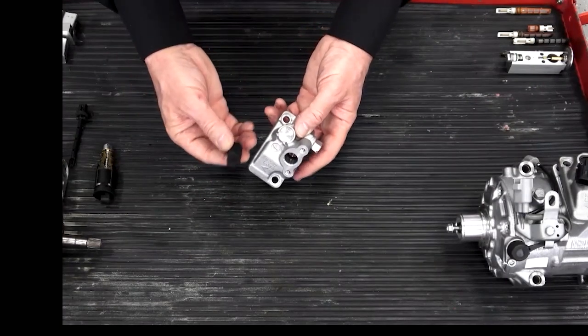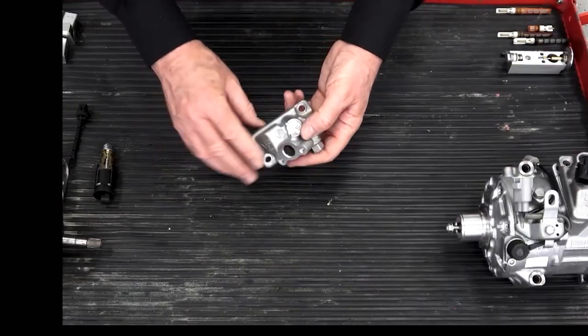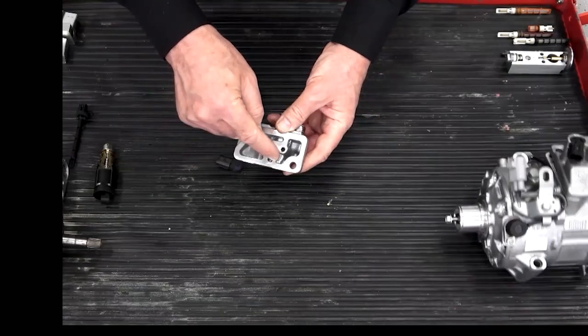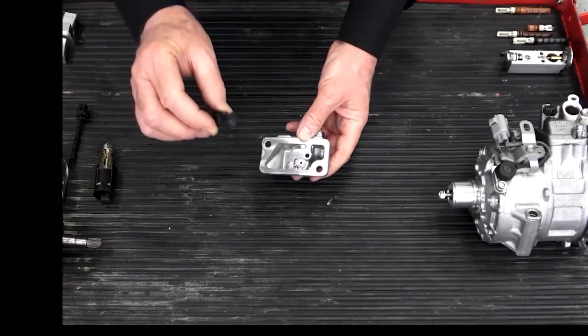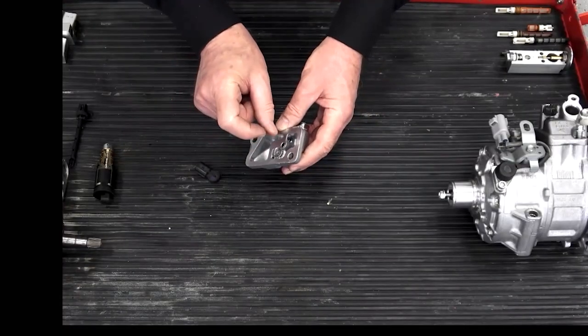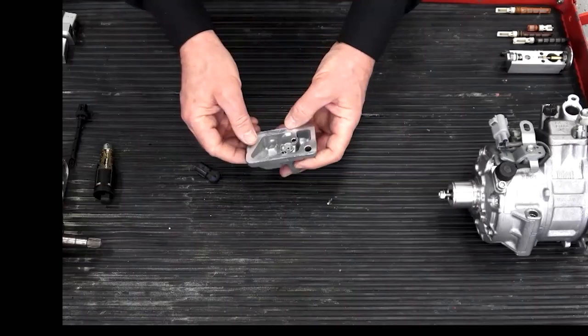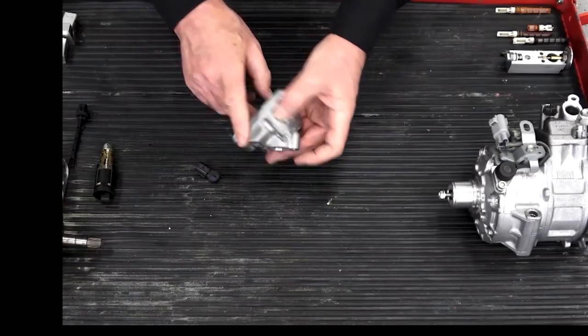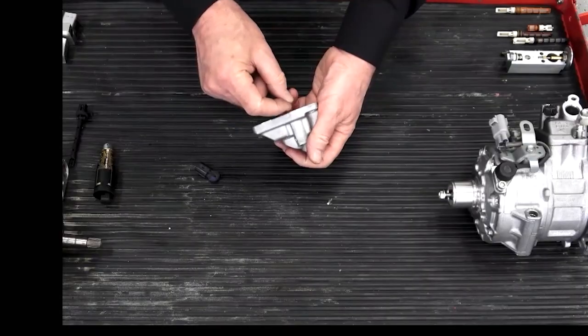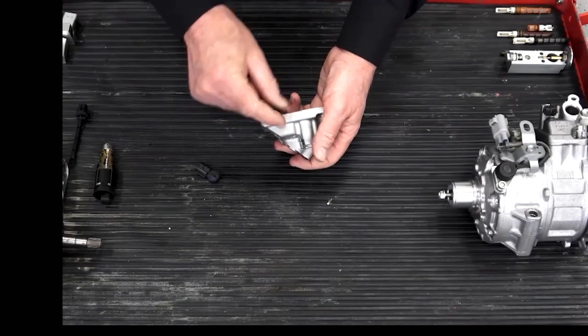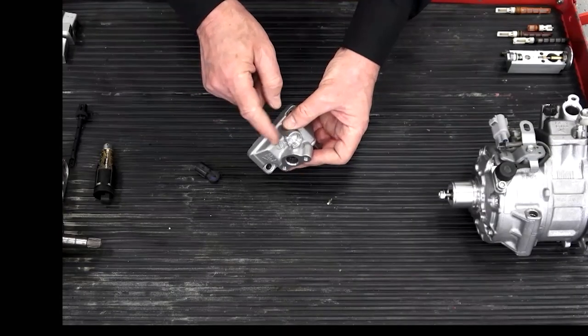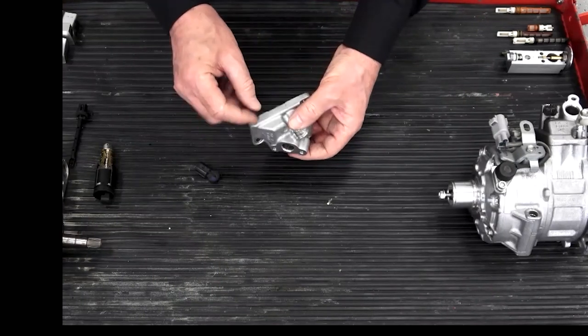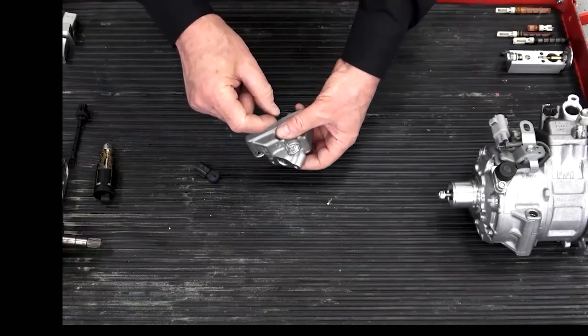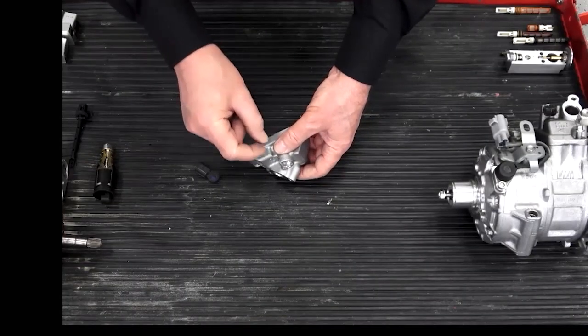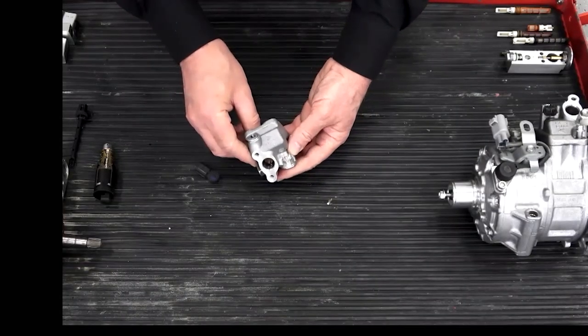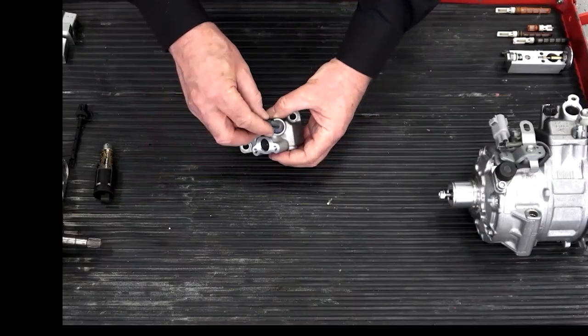The sensor does not contact the refrigerant itself. Inside, I can't see it here, but just below the sensor, there's a tiny little magnet balanced between two springs. As the refrigerant is forced out of the compressor, there is a shunt passage here. There's a calibrated restriction in the compressor output port, in the discharge port. And so the little magnet is displaced in proportion to the pressure drop across the restriction. That's how this volume flow sensor works.